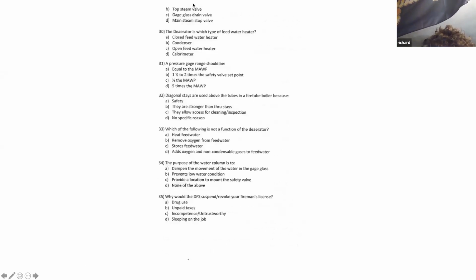Excellent. All right. Greg Lovett, 28. What device prevents the boiler from firing dry, low water cutout? C, the low water cutout is correct. You guys are on a roll. Richard Piper, 29. After replacing gauge glass, which valve is open first? B, top steam valve. Top steam valve. That is correct.